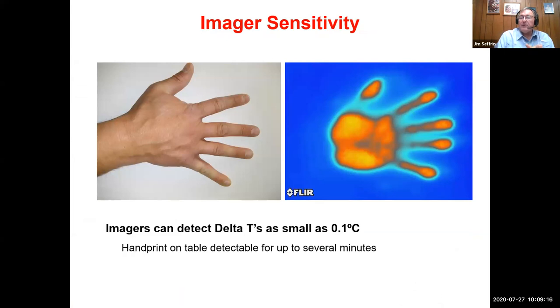Those who have a thermal imager will note that thermal imagers are extremely sensitive to small temperature differentials or delta T's. Thermal imagers can detect delta T's as small as 1/10 of a Celsius degree, or just a fraction of a Fahrenheit degree. You see here a pair of images where a person has placed their hand on a wall surface for a few seconds and then removed it. And using a thermal imager, we can see the thermal handprint that is left behind. That handprint, whether it be on a table or on a wall, can be detectable for up to several minutes after the hand has been removed.